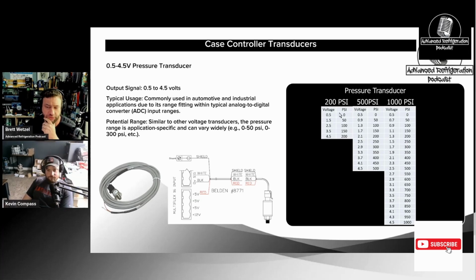And that's what I made. They have these tools on your phone called the linear interpolator. There's Linear Interpolator on Android, and then Interpolation Master, I think it's called, on the iPhone. And you can put in these values. It'll ask you for a start value. You always put your voltage on your left because it works better that way. So I would start by saying, okay, I'm putting 0.5, and then on the other axis, it'll ask what are we reading on that? So 0 would equal 0.5, and then put the end rating in, which is 4.5 to 200. Then you can put in your mystery voltage of what you're getting at the board, and it should spit out a pressure of where it should be based on that interpolation of those numbers.